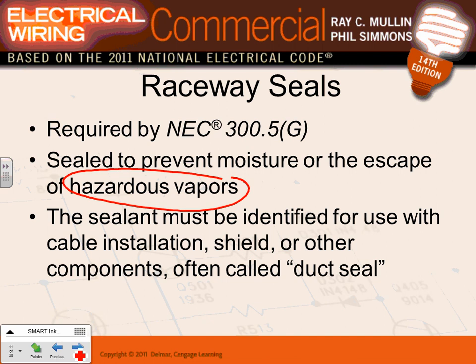When you put a sealant, the last thing you want is for the compound's chemicals to eat into the insulation of your conductor. The sealant has to be identified for the insulation type. Duct seal is a common compound used. It has to be compatible with the insulation. If you seal against water but damage your insulation, you're going to have an arc flash or short circuit.